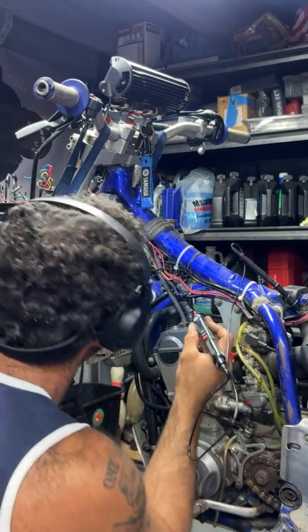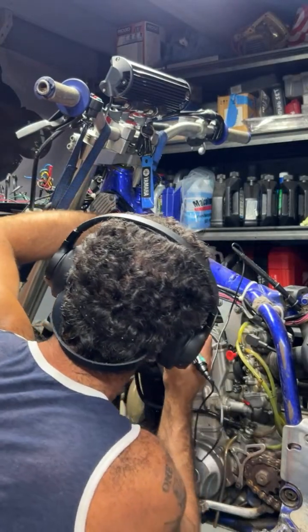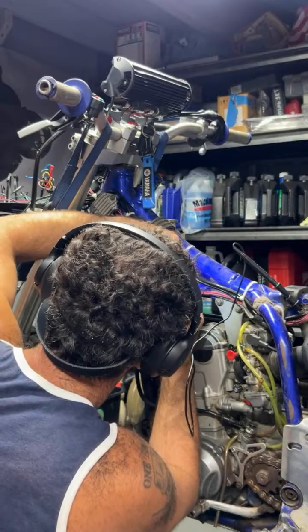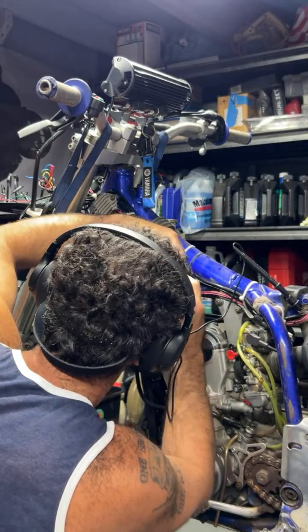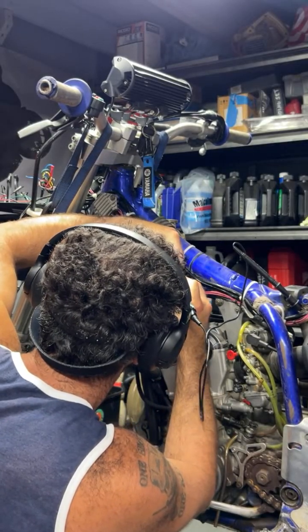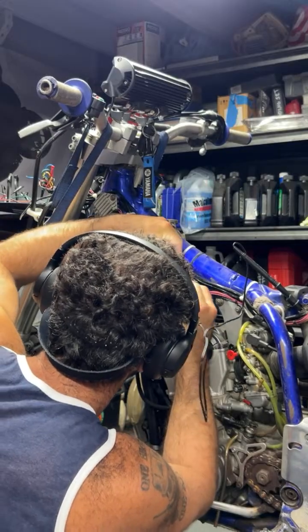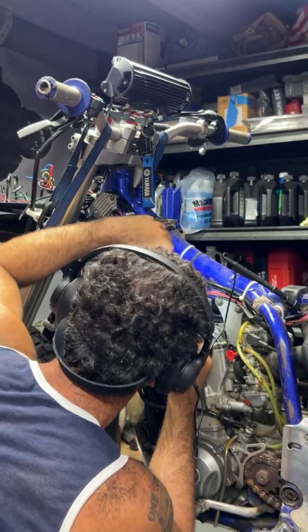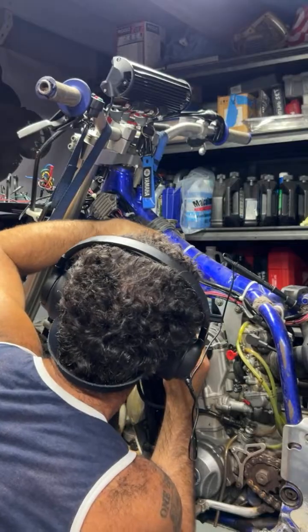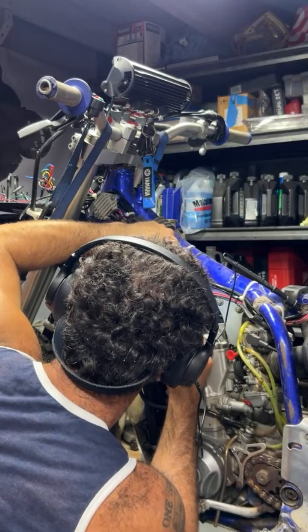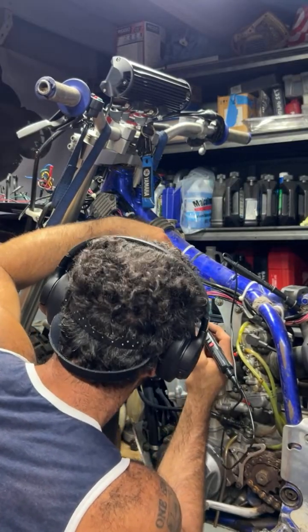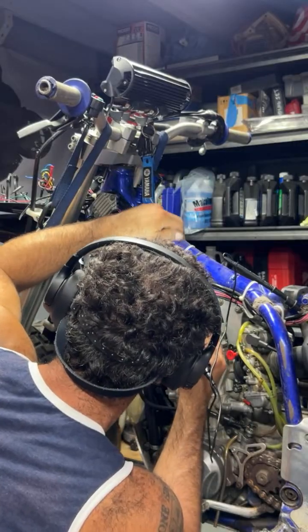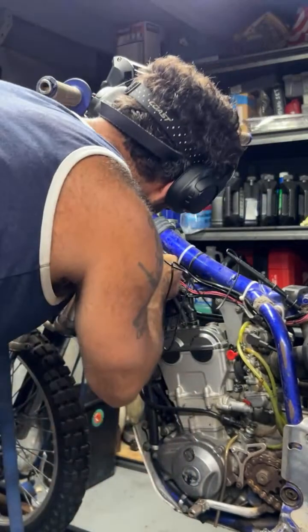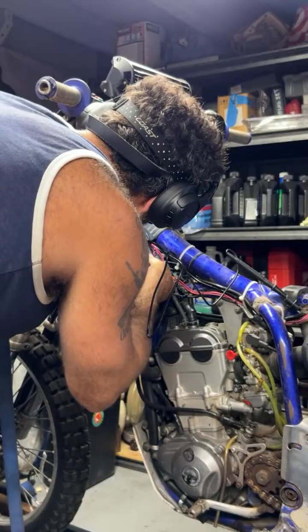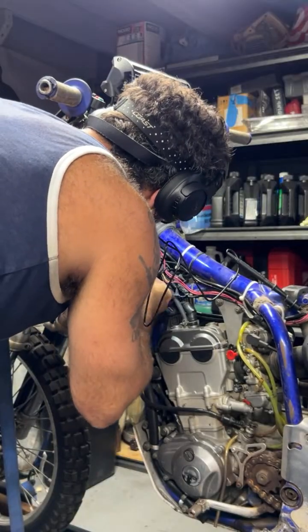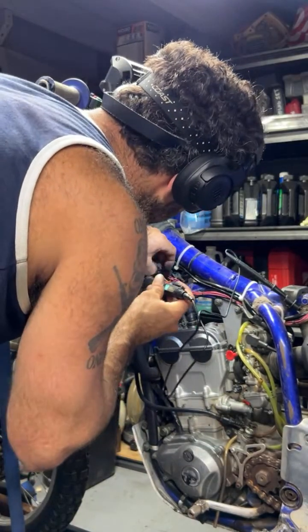All right, got continuity there. Let's redo this test. Ooh, that's grounded out, and that's grounded. So that looks like a ground though, but that yellow one, that's coming off the stator. That should be a hot leg, I'm assuming, because this right here goes into the rectifier here. Yeah, so...